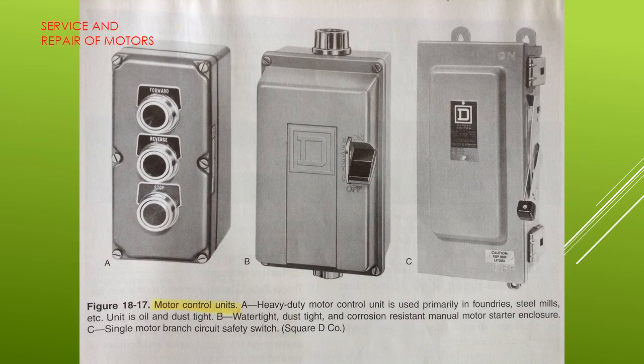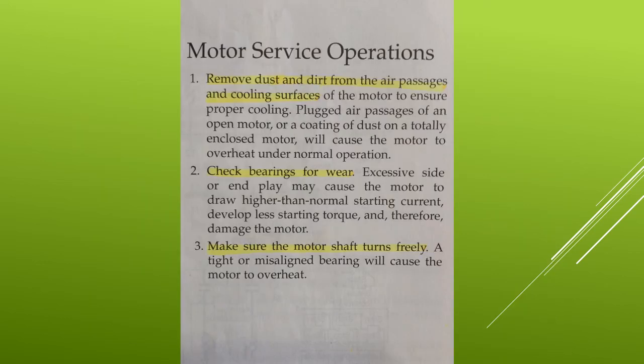Various types of starter enclosures and their applications are shown in figure 18-17. A well-made and properly installed electric motor requires less maintenance than any other type of electrical equipment. However, for the best and most economical performance, periodic service is required. The service operations listed should be performed once a year or more often if the motor operates under conditions of severe heat, cold, or dust. Motor service operations.